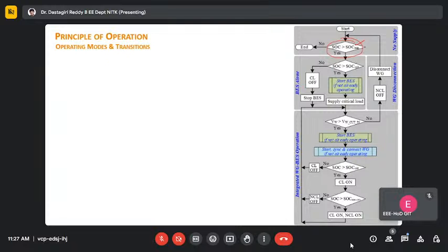You should always check this now and then. If it is not already started, then you should start the battery first. Without battery, it is tough, so we always recommend starting the battery converter in the beginning. You can start the diesel generator first, that's not a problem, but synchronizing the battery afterward is also not a problem, you can do that. So we started with the battery.